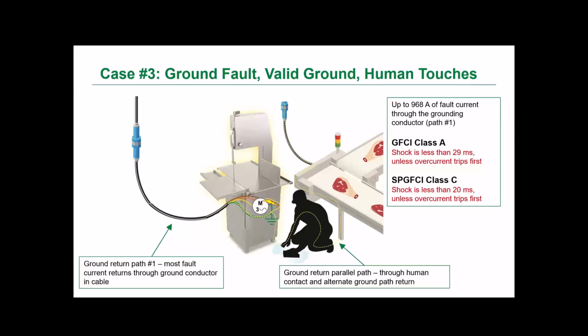Now, this is how the low resistance path of that grounding conductor is important, because the person touching the equipment is in parallel to that equipment grounding conductor. So the shock current that they will receive will be based on the ratio of their body resistance to that equipment grounding conductor. So in these cases, the devices are seeing the same current, but as we talked about before, because of the different maximum trip points, there is a small difference in the reaction time.